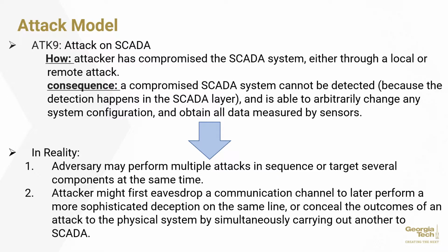Attack number 9 is similar, in that a control element is directly attacked, but this time the SCADA, and usually the attacker has compromised the SCADA system either through a local or remote attack. Consequently, a compromised control system such as the SCADA system cannot be detected, because the detection happens in SCADA itself, and the attacker is able to arbitrarily change any system configuration and obtain all data measured by sensors.